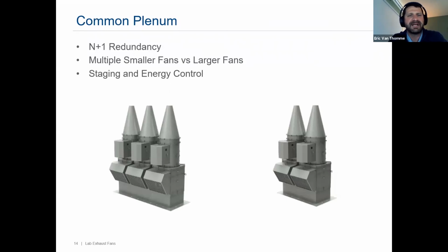I mentioned it on the previous slide a little bit, but we do build common plenums where you can install multiple fans on the same plenum mixing box. This gives you greater flexibility for staging and energy control, and that N+1 type redundancy that I mentioned before. This also gives you the ability to utilize multiple smaller fans instead of just one larger fan. Now there is a little bit of an efficiency trade-off anytime you're talking about smaller fans versus larger fans. Larger fans are always more efficient than smaller fans. But when staging and energy control are of utmost priority, you may trade off individual fan efficiency for the overall system efficiency and flexibility from a staging and energy control standpoint.